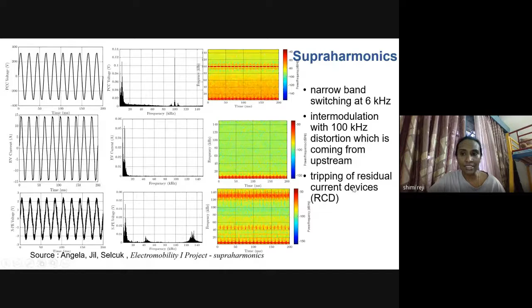In the neutral and protective earth also, this 6 kilohertz component was seen. So when this goes through the neutral and protective earth, it may result in unnecessary tripping of the RCD. That study was also done.